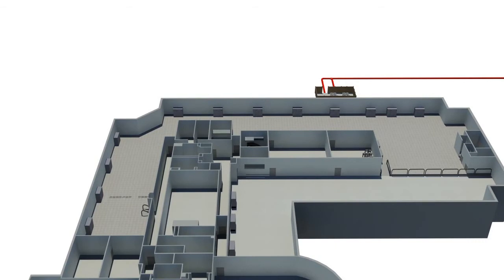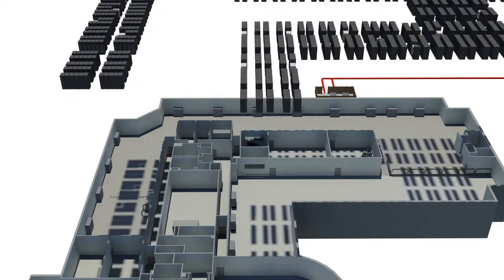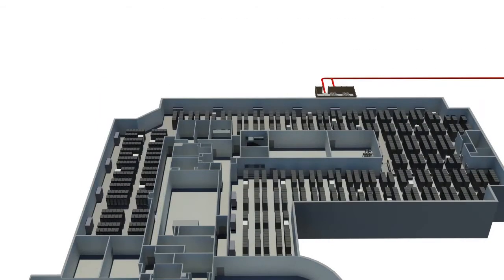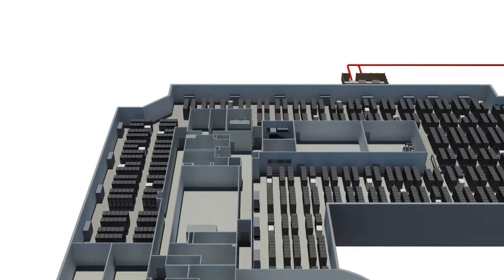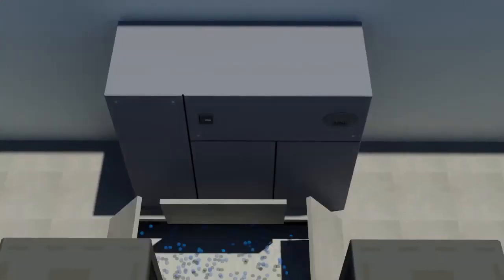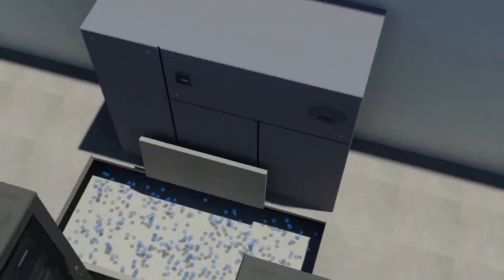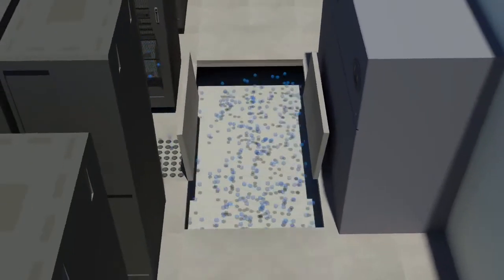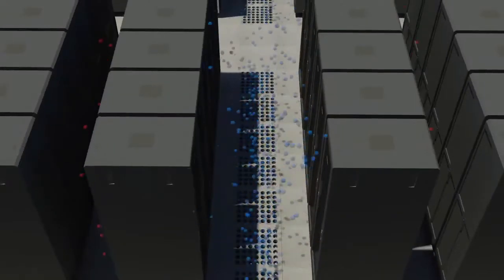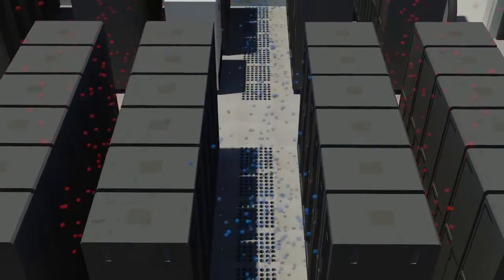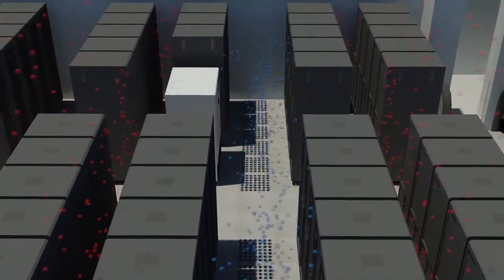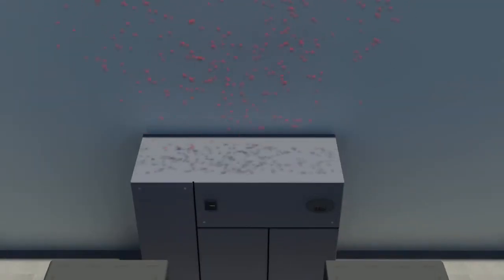72 degrees Fahrenheit. Server cabinets are positioned in parallel rows, back-to-back, creating a hot aisle, cold aisle configuration that efficiently keeps hot air circulating out of the cabinets and cool air circulating in. Cold air is pushed from the computer room air conditioner unit and ducted into the cold aisles. That chilled air is pulled in through the front of the server cabinets and then fanned back out as hot air in a hot aisle. The hot air rises to the ceiling and then enters the hot air return for the cooling process to start again.